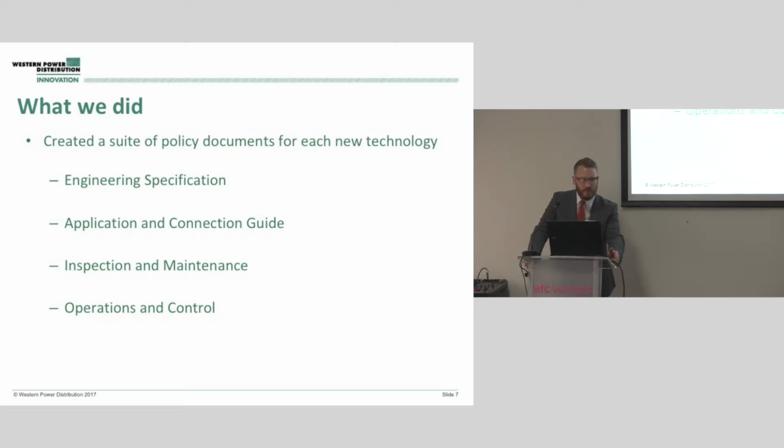So we make sure that no matter where it is on site, people are switching off the right bits, isolating, earthing, either engaging or disengaging the right level of protection before and after they've worked on it. And it also facilitated wider control in terms of the remote control room functionality, so control engineers could take a more practical and pragmatic approach to how they were going to operate for alarms and trips that happened principally outside main working hours.